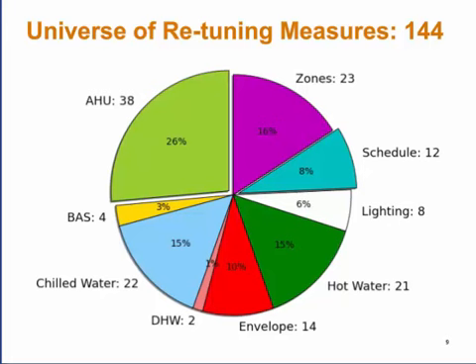So what does the universe of retuning measures consist of? We have about 144 measures, categorized into various groups. For example, on air handlers we have 38 different measures. These aren't problems with the equipment itself, but issues related to our inability to properly control that equipment or optimize and manage the control sequences. For example, on air handlers, a measure would be a lack of static pressure reset or a lack of supply temperature reset. There's a much bigger presentation, about 60 slides, covering all of this in detail, with a link at the end if anyone wants to download it.